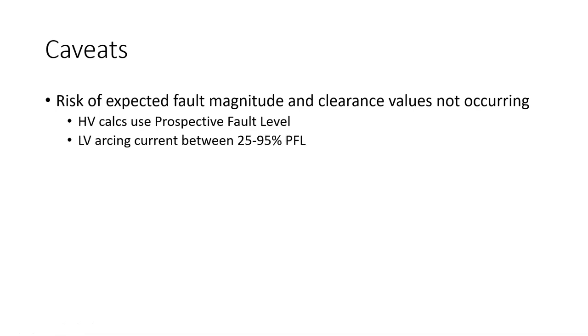But with low voltage, NENS 09 says that LV arcing current can be anywhere between 25 to 95% of the prospective fault level. Some of you might remember AS3000 quotes this figure as being 30 to 60% of the fault level. So NENS says, okay, we're going to do our calculations based on AS3000, which stipulates use 30% of the prospective fault level.